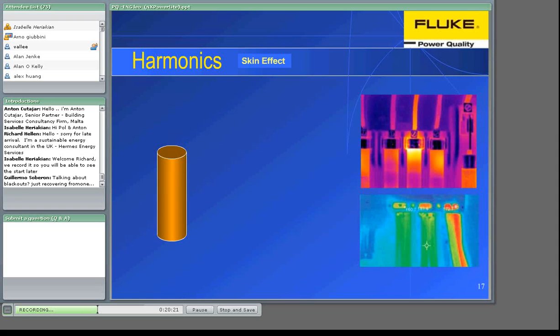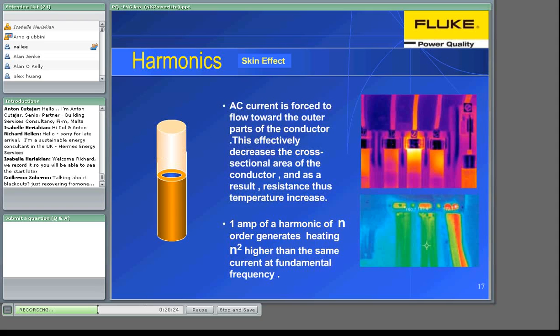Skin effect. An alternating current tends to flow on the outer surface of the conductor. This is known as the skin effect, and it is more pronounced at high frequencies. The skin effect basically decreases the effective cross-sectional area available for the flow of current, thereby increasing resistance with heating. We can say that above 350 Hz it might become significant. Now, to help overcome this problem, multiple cable cores or laminated bus bars can be used.